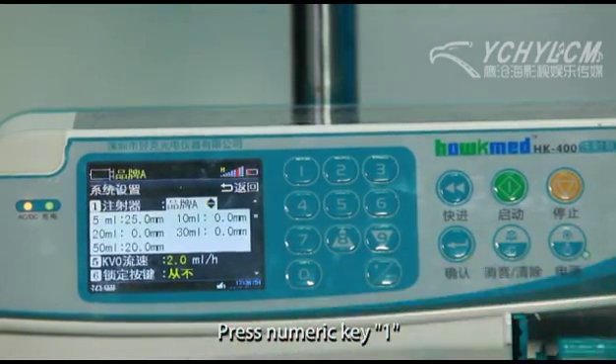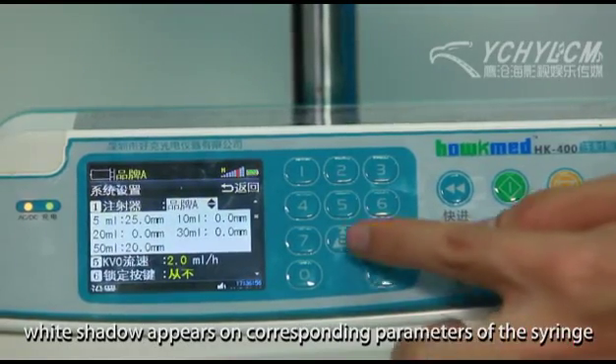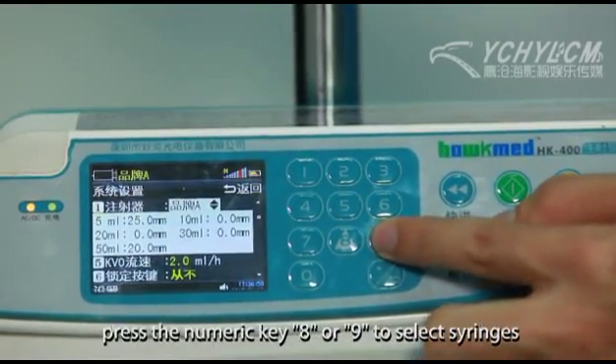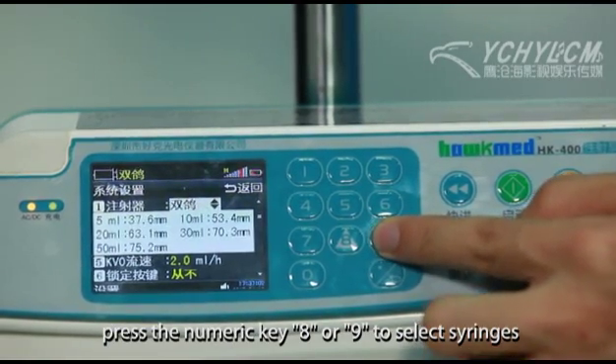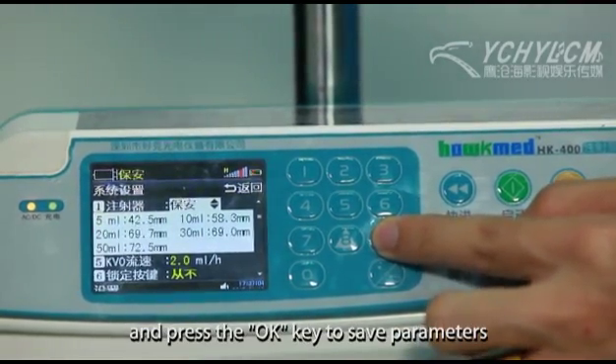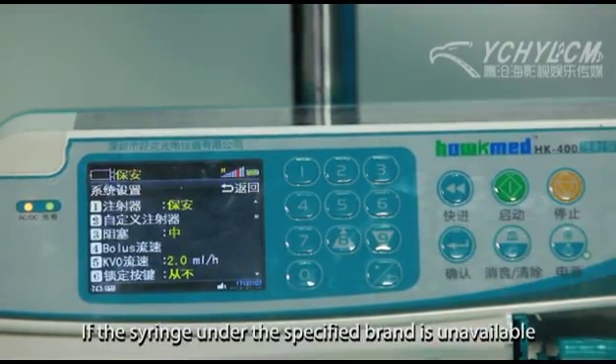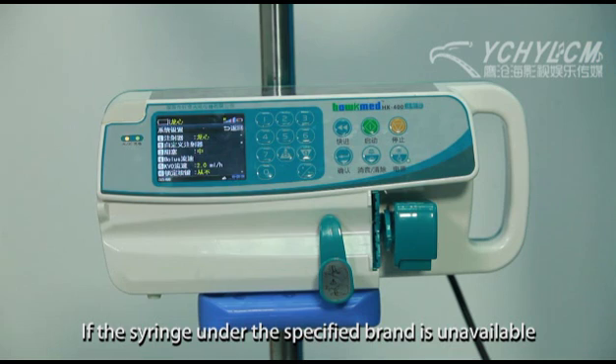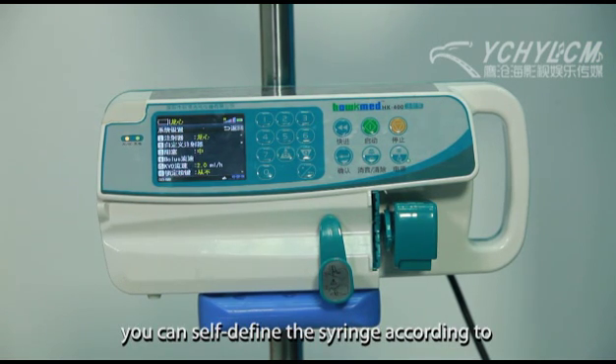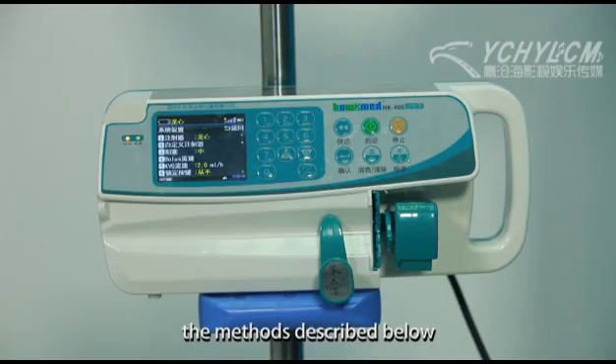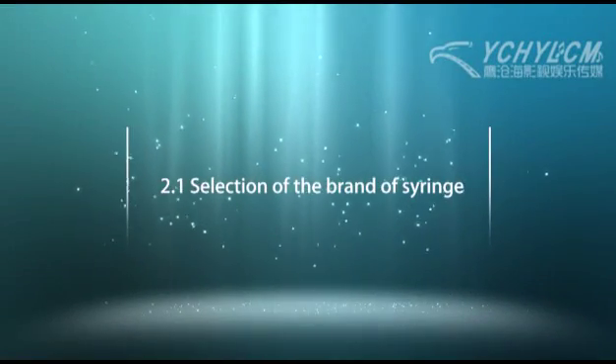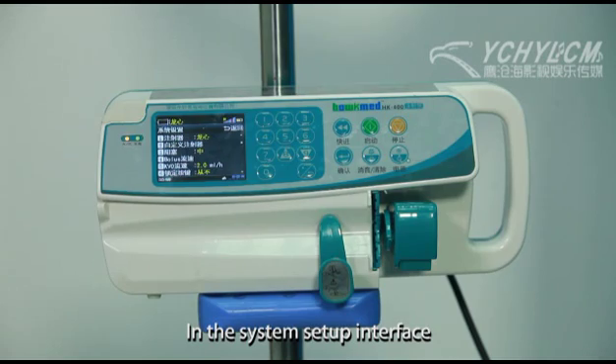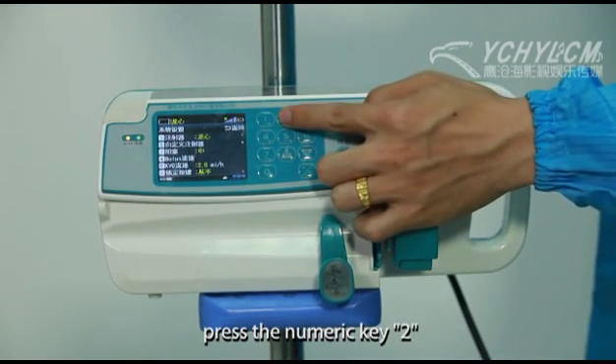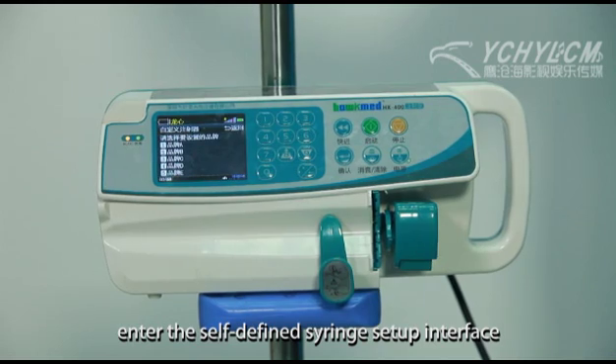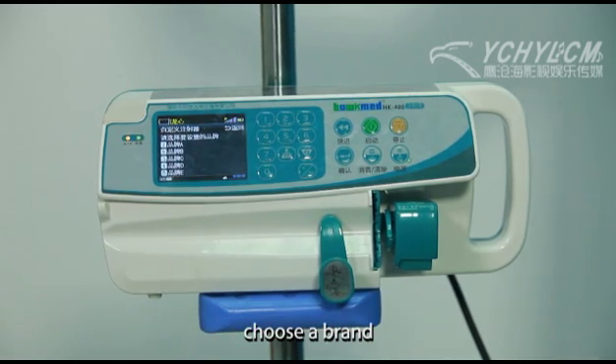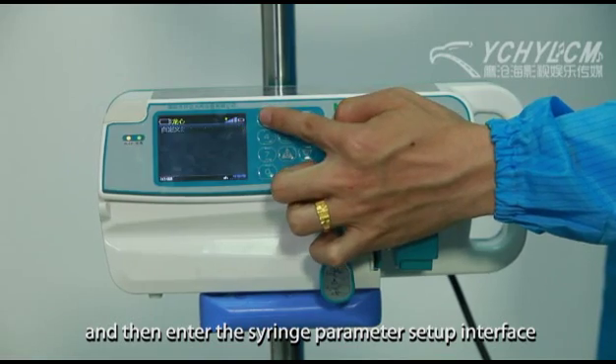Press numeric key 1. White shadow appears on corresponding parameters of the syringe. Press the numeric key 8 or 9 to select syringes, and press the OK key to save parameters. If the syringe under the specified brand is unavailable, you can self-define the syringe according to the methods described below. In the System Setup interface, press the numeric key 2, enter the self-defined syringe setup interface, choose a brand, and then enter the syringe parameter setup interface.